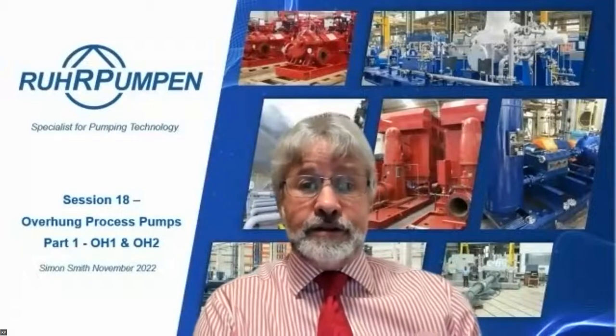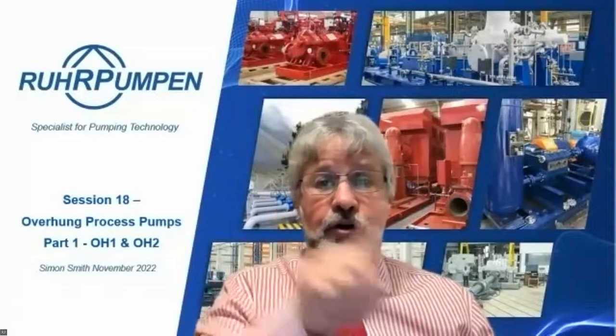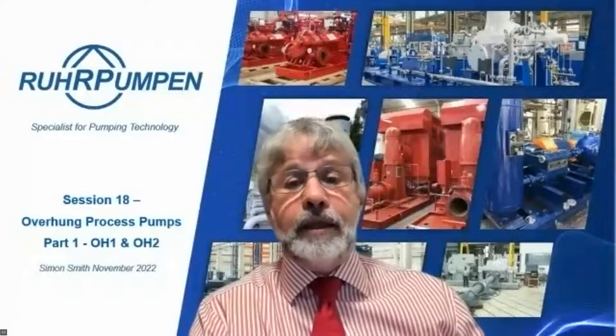Carl Hoag says again, is axial thrust force significant, and how is it resolved in both these types of pumps? That's a nice question. Yes, and it's the same answer in both. The thrust is balanced by having balance holes in the impellers, which equalize thrust across either side of the impeller. For very high suction pressures, those balance holes might well be plugged. And for higher pressures, higher thrusts still, there will be different types of thrust bearing that can be fitted.